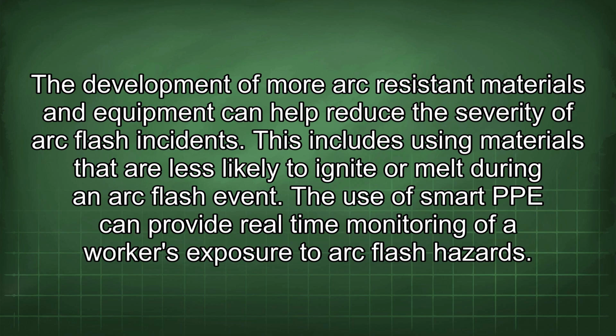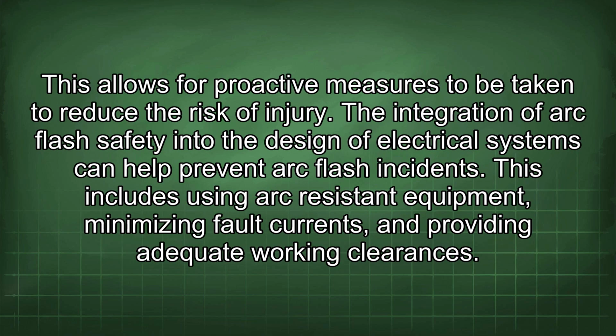The use of smart PPE can provide real-time monitoring of a worker's exposure to arc flash hazards. This allows for proactive measures to be taken to reduce the risk of injury. The integration of arc flash safety into the design of electrical systems can help prevent arc flash incidents. This includes using arc-resistant equipment, minimizing fault currents, and providing adequate working clearances.